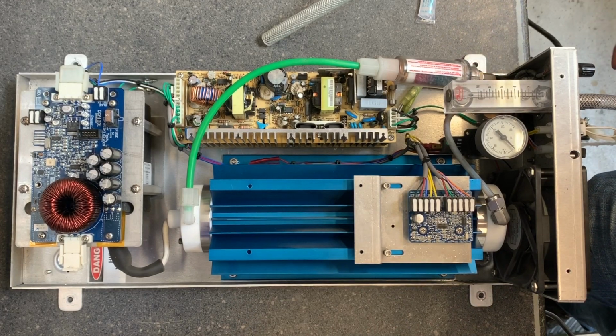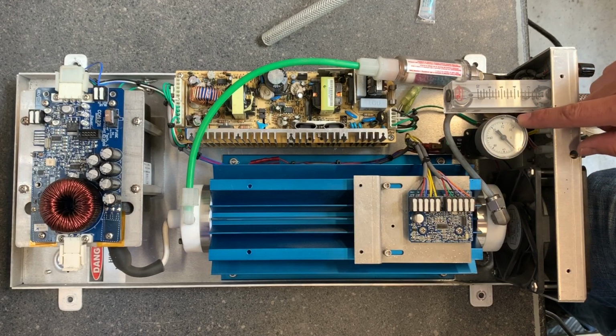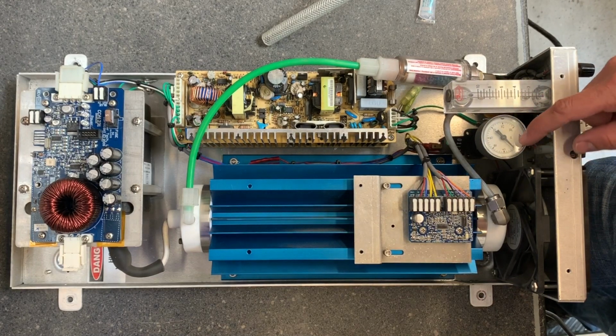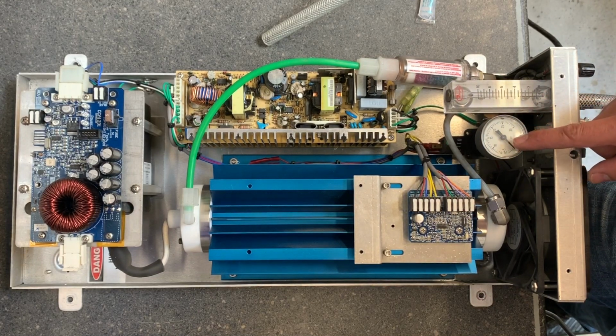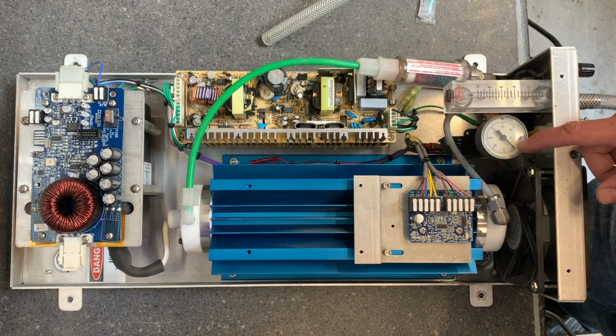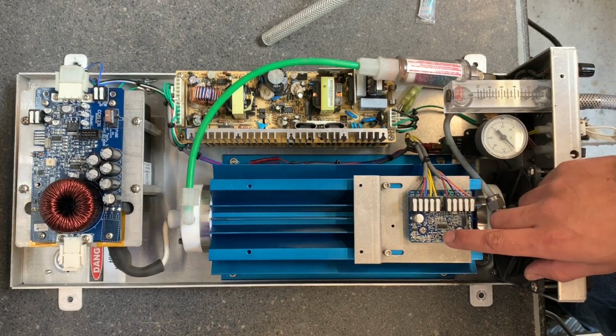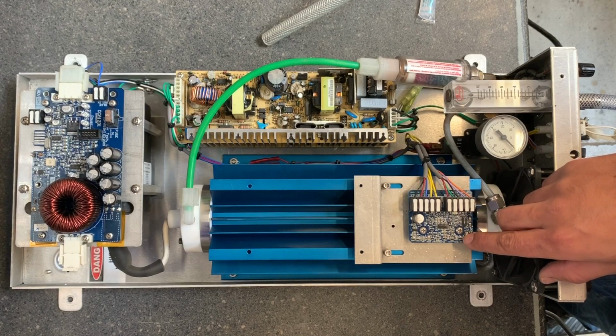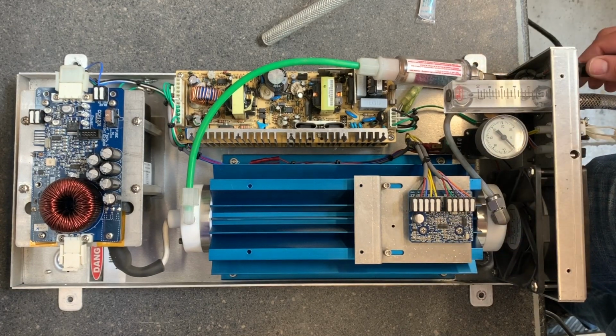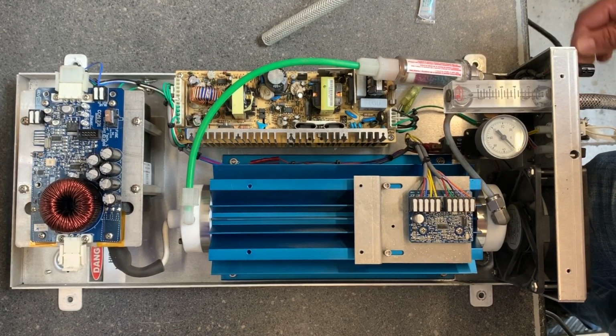So for this unit to work, you have to satisfy the pressure switch. We recommend 8 psi to satisfy the pressure switch. Once you satisfy the pressure switch, it will bypass the 4-20 milliamp controller and it'll go into manual, which then you will control with your potentiometer. Make sure it's turned all the way to the right so it's producing.